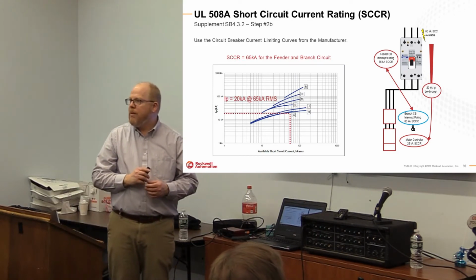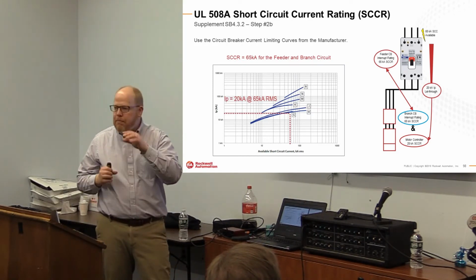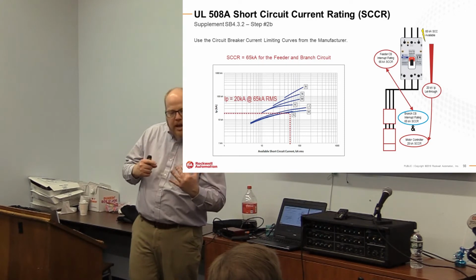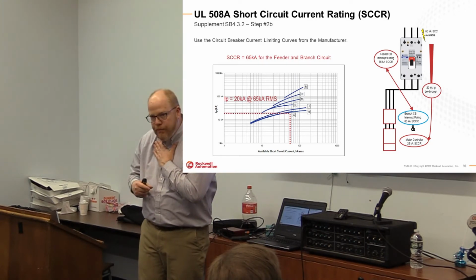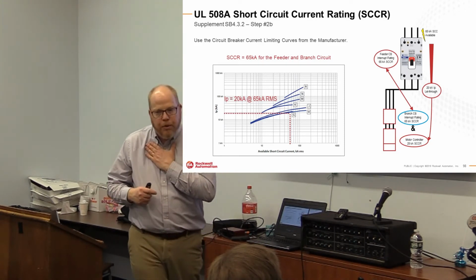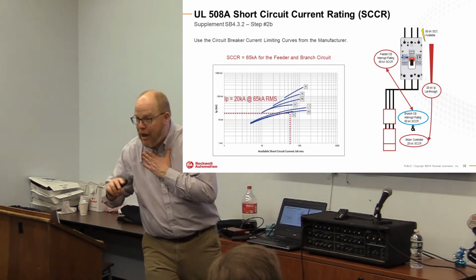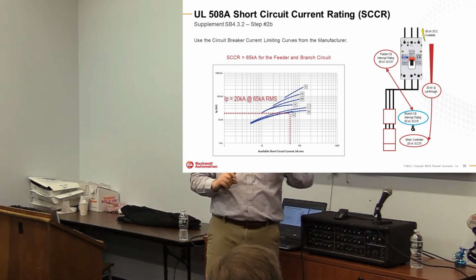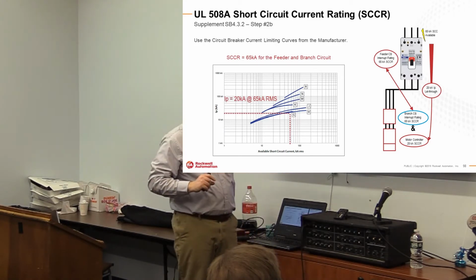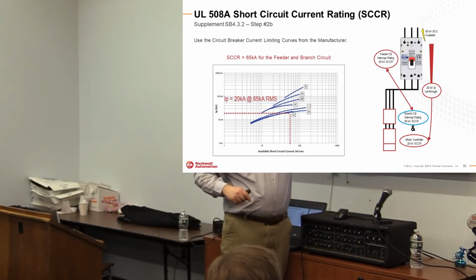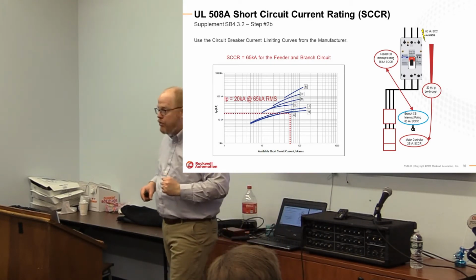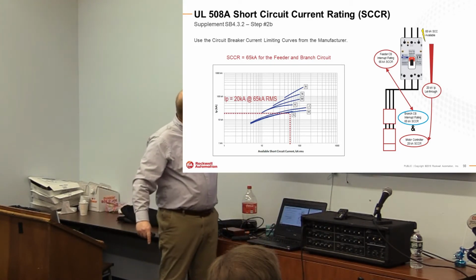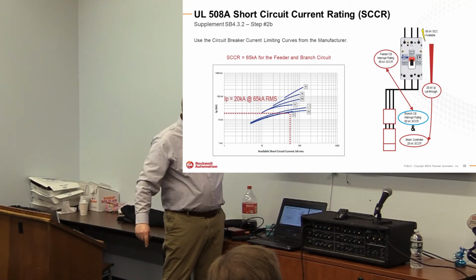All right, so let's talk about this. One of the pieces of data, a lot of people ask me, where do I get this data? You get that from us. A breaker vendor will provide you with those 2 pieces of data. You're allowed to use the manufacturer's curves for this evaluation. So here's an example of one. This 65,000 amp rated breaker has a 20,000 amp peak let-through. That data is derived from the trip curves that you get.